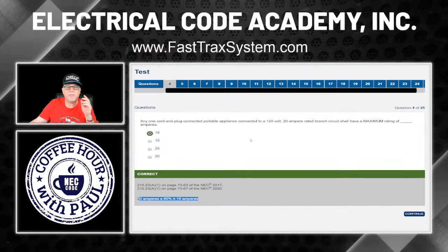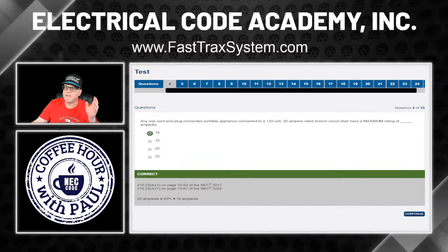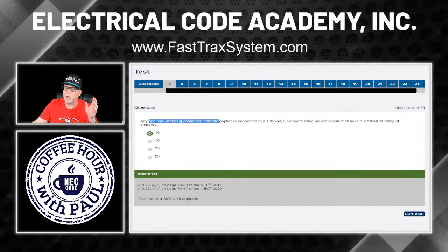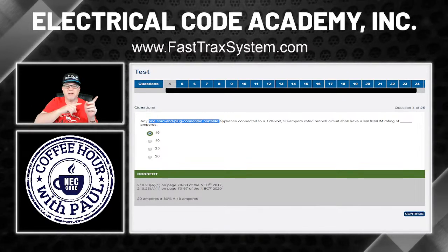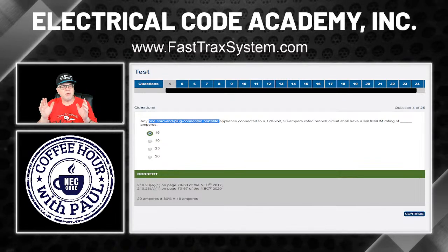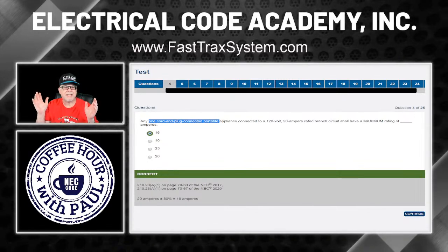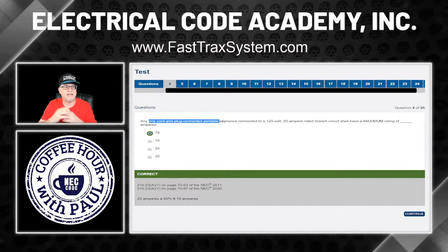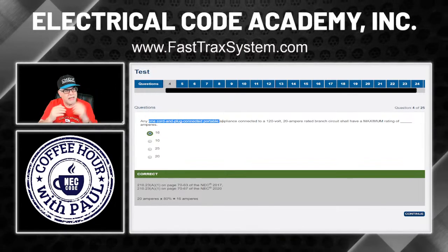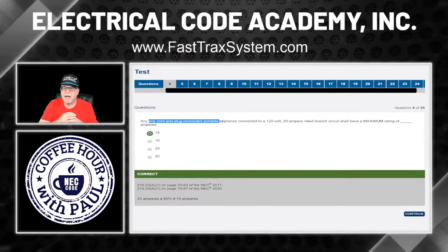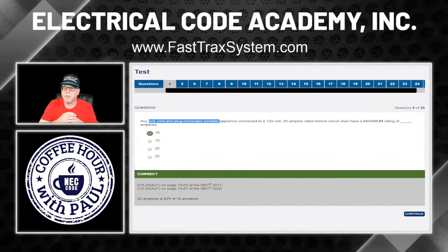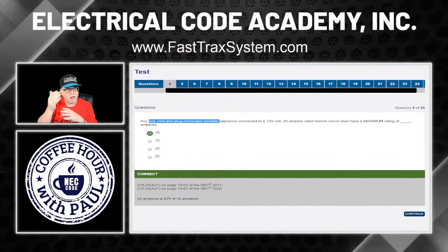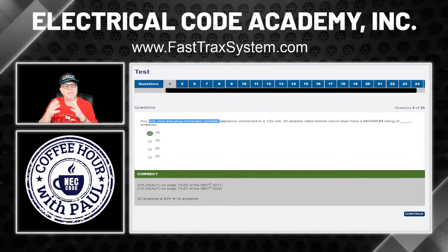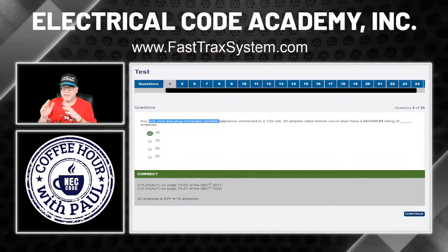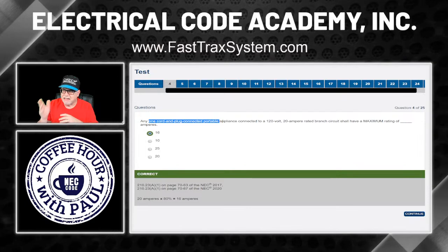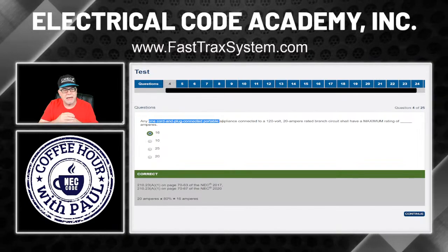Now, why did this trigger this one? Well, because it said cord and plug connected portable. That tells me it's not fixed in place. That's not to be confused with any branch circuit typically in a house. If it's 15 amps, I can put 15 amps on it. If it's 20 amps, I can put 20 amps on it. But since this is a cord and plug connected portable appliance that's going to be plugged into that, we have this threshold we have to follow, and it's not to exceed 80%. And that's what we got in 210.23(A)(1).